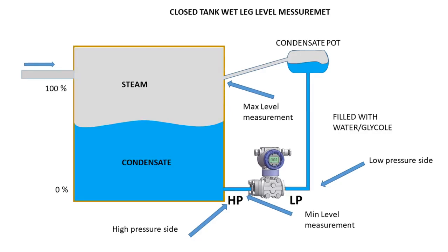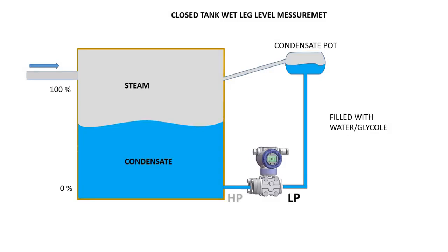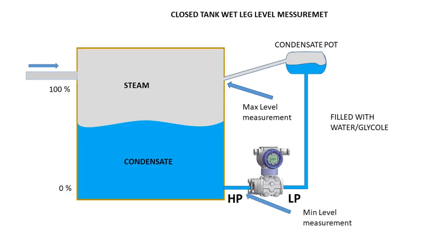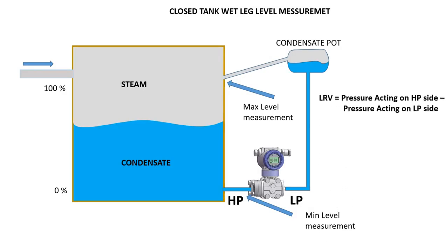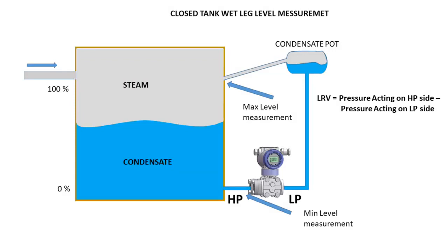It will minimize the error and give an accurate reading. So how do we calculate the calibration range of the transmitter? First we have to connect the impulse line to the transmitter. The high pressure side of the transmitter connects to the bottom of the tank, and the low pressure side connects to the top of the tank through a condensate pot. For measuring level, we have to calculate the LRV and URV for the transmitter. The equation is: LRV equals pressure acting on the HP side minus pressure acting on the LP side.